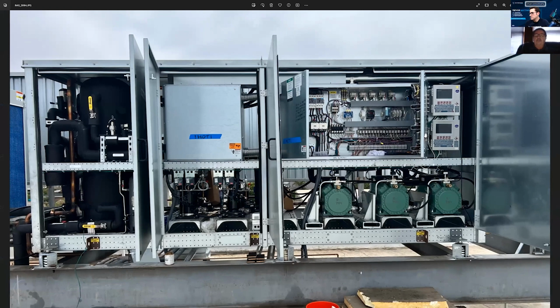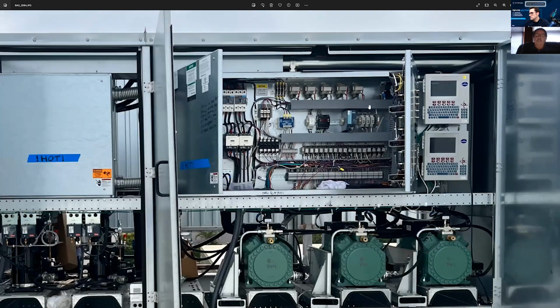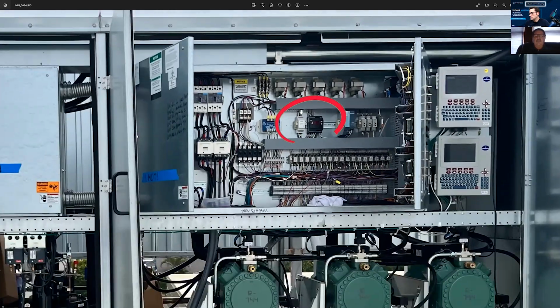Yep. I'll go up to the right and go to the 326A. So this was being controlled by a 326A, not by an iPro. If you have gas bypass valve issues, and most of the time this valve wants to go to the closed position, if you start having issues with it, on the bottom right are wires 21, 22, 23, and 24. It's going to be white, black, red, and green. Those are your stepper valve control wires. White and black, one set, red and green are the other.